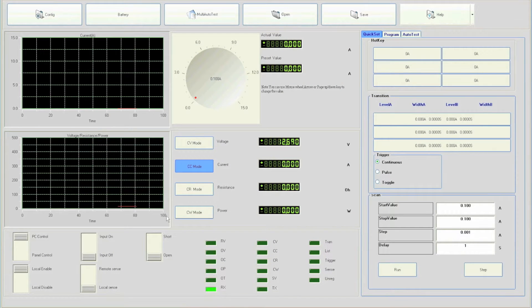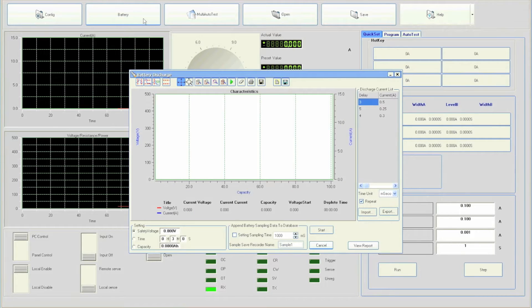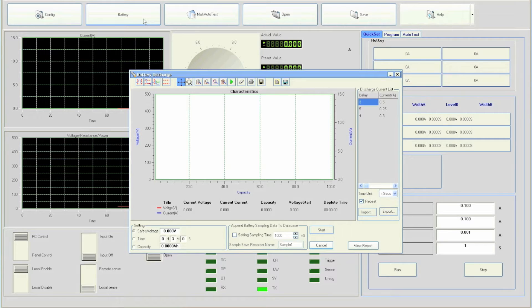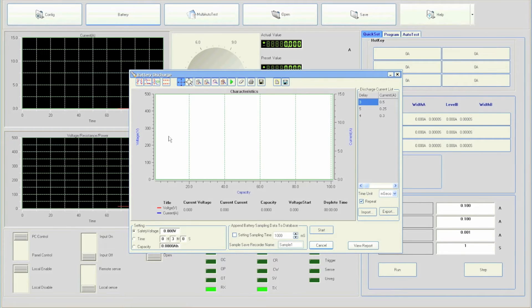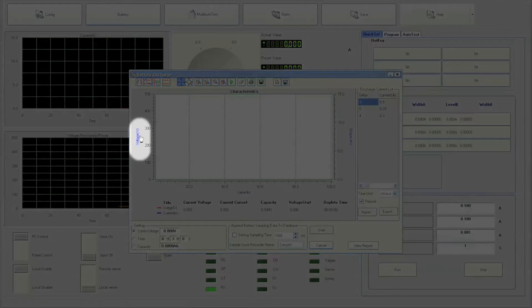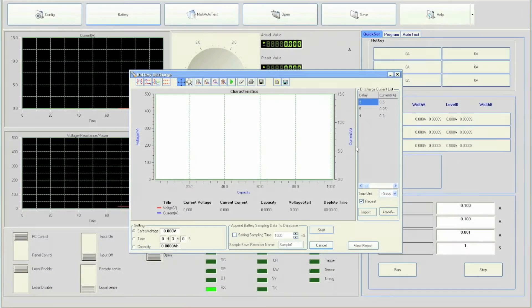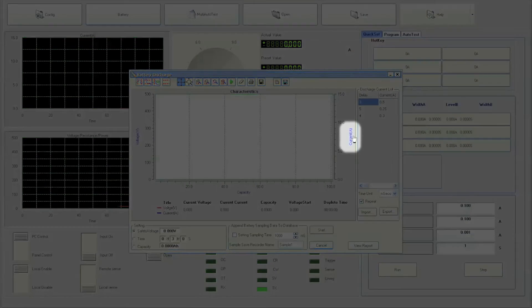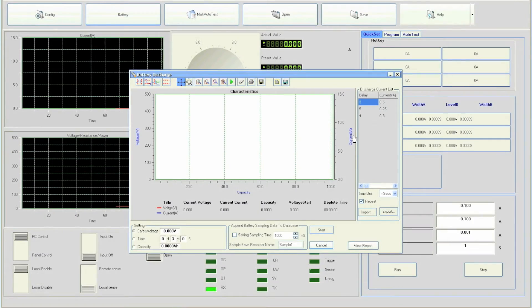Now click on the battery button at the top to enter the software battery test function. The battery discharge window will open and the main screen illustrates a graph with labels for voltage, capacity, and current.